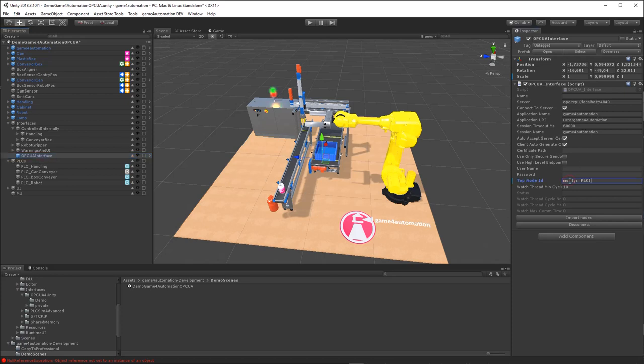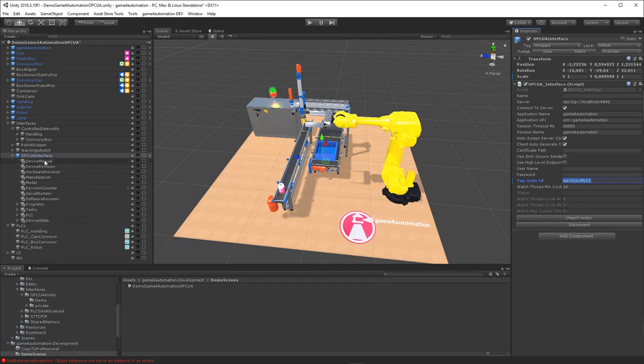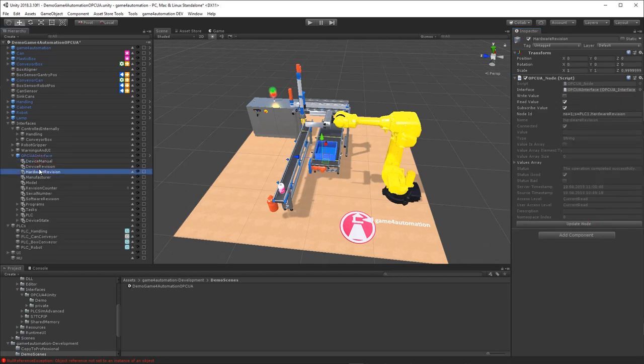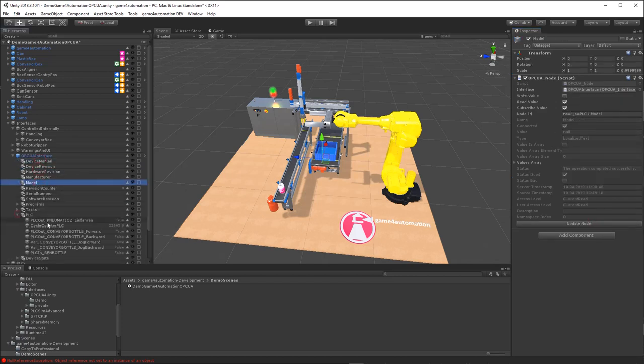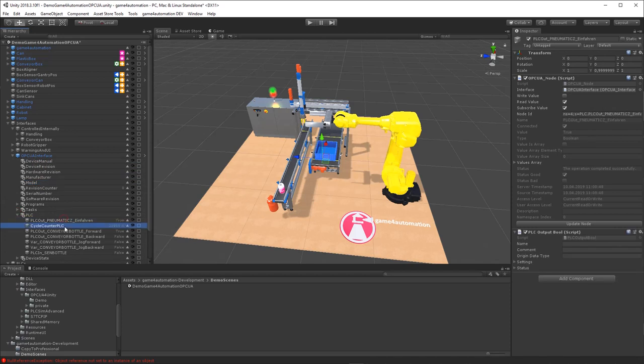The most important ones are the address of the OPC UA server and the node ID of the top node we want to browse. Now we can import all nodes, and we have here all nodes which are under this top node available on the OPC UA server.